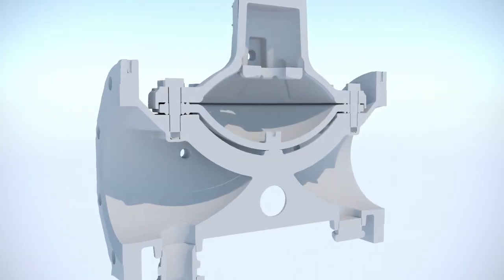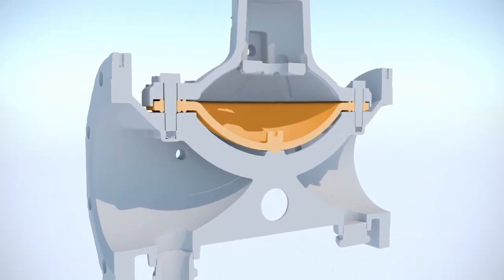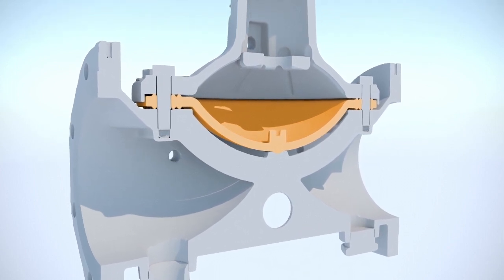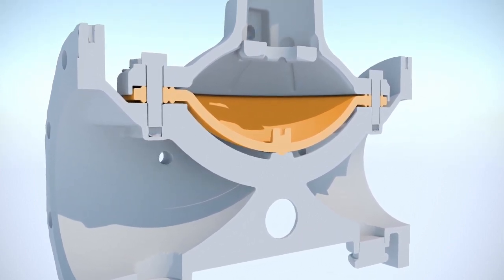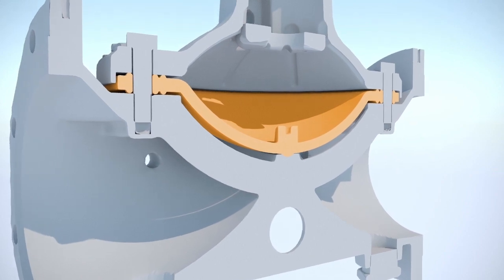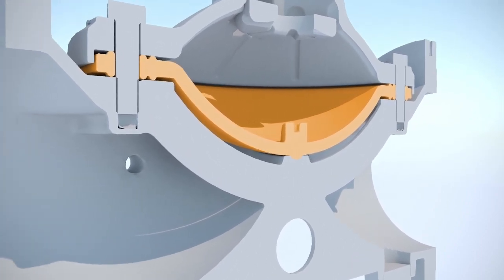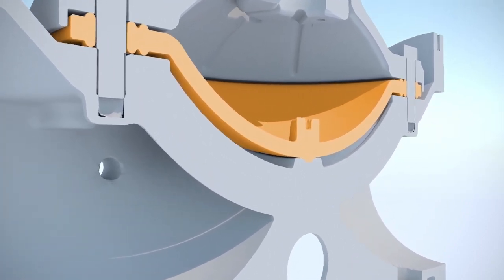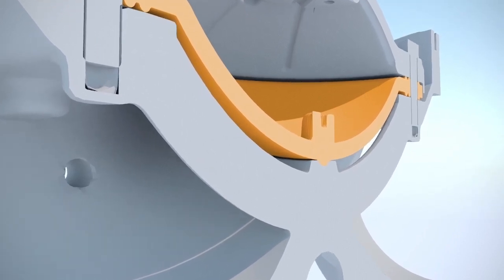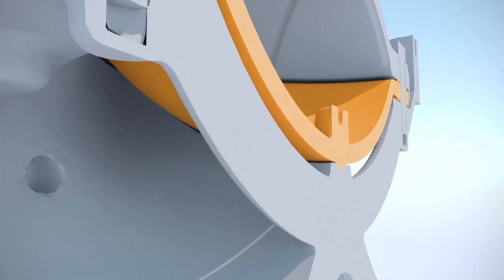It's a perfect seal valve by means of an internal membrane in reinforced EPDM which makes it immune to deterioration due to foam or aggressive chemicals in the firefighting water, certified by a third party for class 6 ANSI FCI 70.2 and IEC 60534.4.